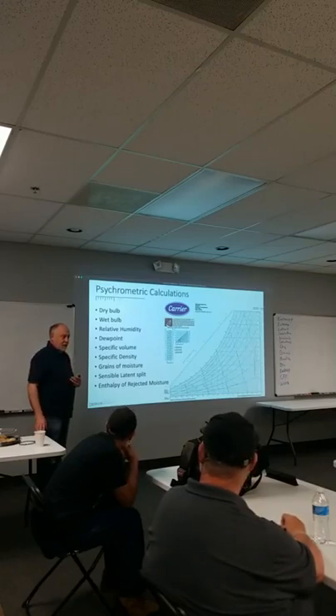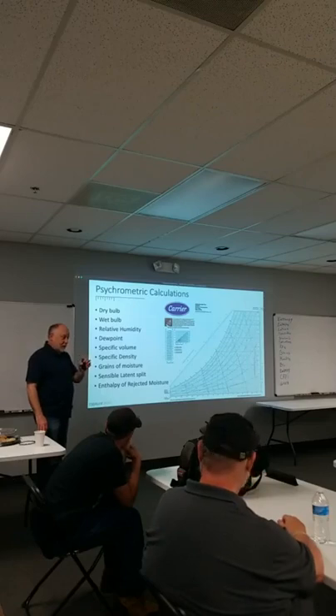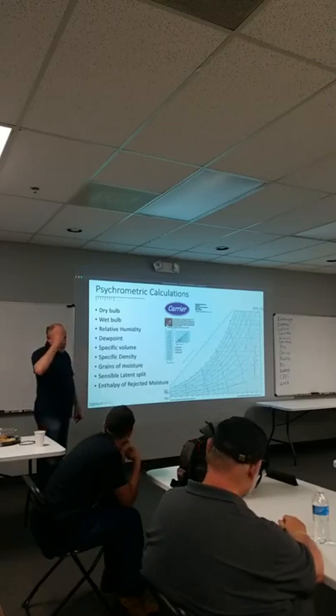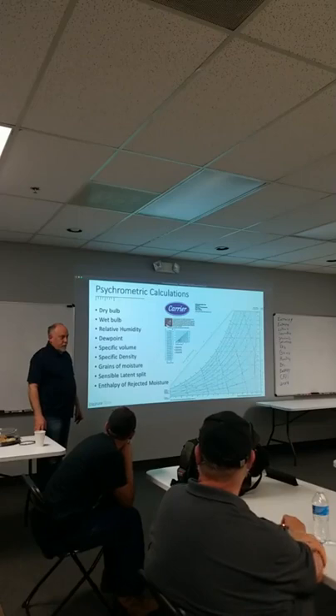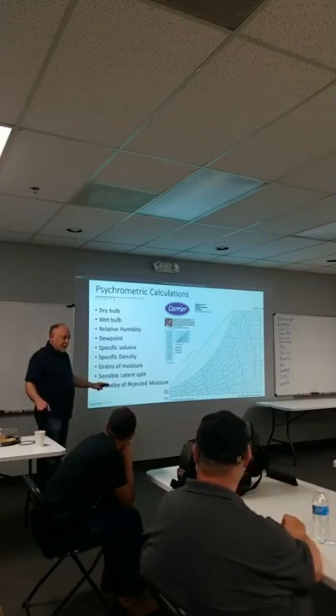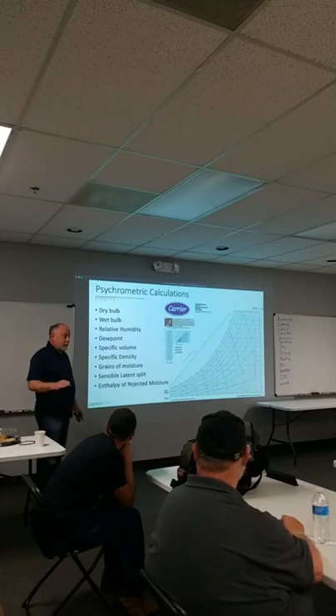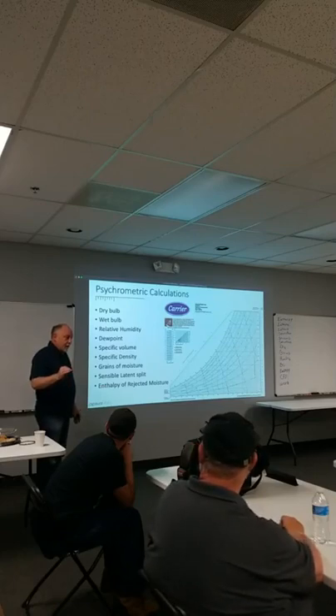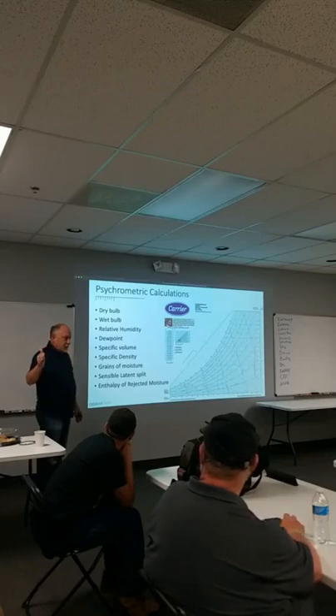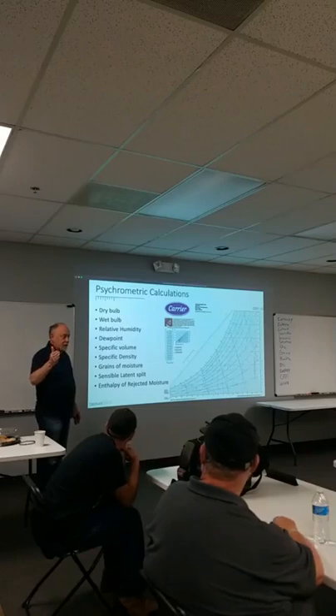Of course there is. Have you ever run a vacuum pump? That's dry air. Well, you are correct, actually. There is no such thing as 0% relative humidity in the air. We can never get all the moisture out of the air. Now, in Arizona, they can run near zero, but you just have to keep moving the decimal place, because we can never get all the moisture out of the air. It adheres to the wall surfaces, a process called adhesion. But in our industry, when we're talking about zero, we're talking about 0.0.